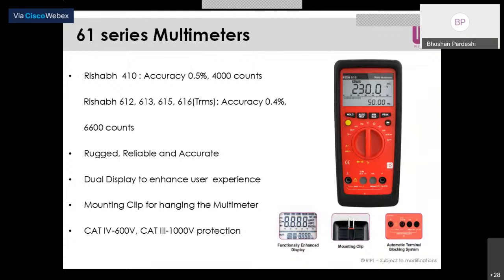If I compare an average multimeter and a true RMS multimeter reading, I'll find a variation of 6 to 7 volts. This is because of harmonics—the more harmonics and the higher their value in the system, the greater the difference between the average value and the true RMS value. Harmonics are nothing but integral multiples of the fundamental waveform.